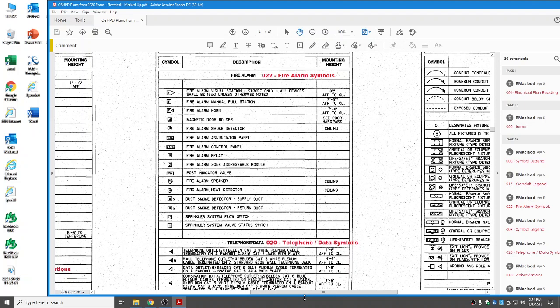I'll see if I can present something at the end of this one here that shows some of the newer fire alarm symbols. Okay, to start out, let's start at the beginning. The first symbol you can see here is a fire alarm visual station, strobe only. It's for 15 candela. Now 15 is the minimum candelas for the brightness of the strobe lights, and typically, we normally see as high as 110 candelas in some of the larger open rooms.